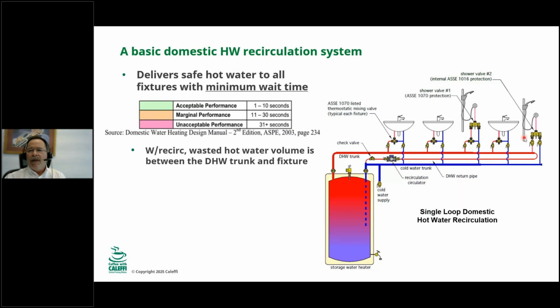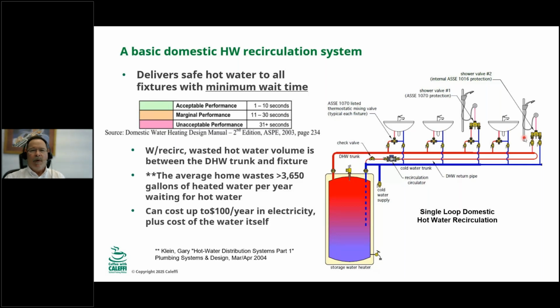So the wasted water, when we talk about wasted water, that's number 2, by the way. Number 1 is wait time. Nobody wants to wait for hot water. Number 2 consideration is the wasted hot water that we're dumping down the drain, because we've heated this water, we've spent money on it, and we don't want to just dump it down the drain. So when we talk about wasted water in a system like this, where we have a recirc loop, what we're actually wasting when we open a fixture is only the water in between the takeoff on the trunk out to the fixture, so it's a small amount.